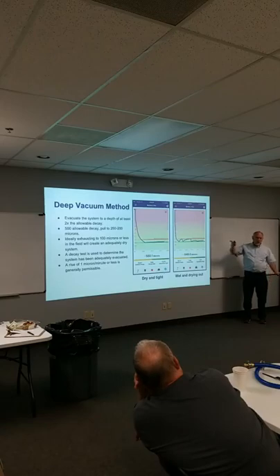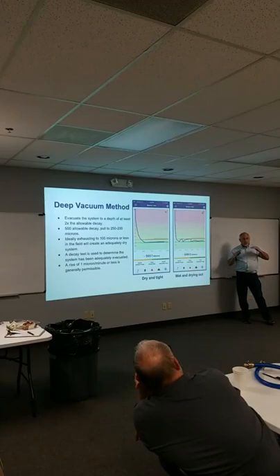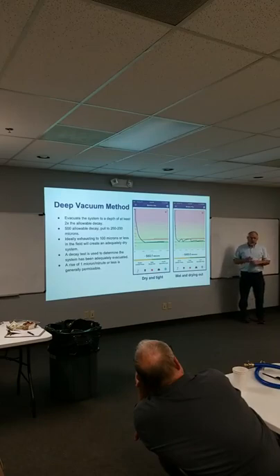On stuff you're servicing, there will be times, I'm telling you straight up, with a 410A system that you've had open for service, you're going to be hard pressed to get under 1,000 microns. You'll evacuate all day, it's just going to stall on you because the POE oil is like a moisture magnet. You cannot remove moisture from POE oil with a vacuum pump, period. It requires a desiccant dryer, so it's critical on 410A that you always change the dryers out.